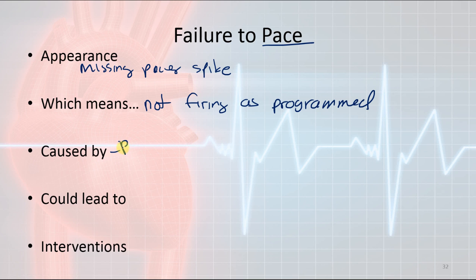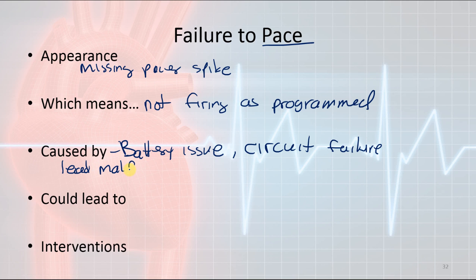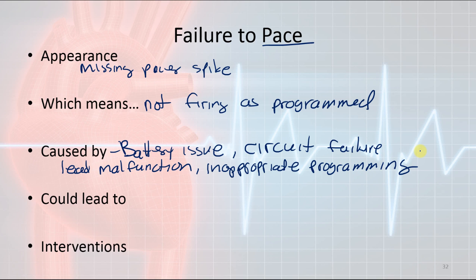This can be caused by battery issues. There could be a circuit failure within the pacemaker itself. It could be a lead malfunction. It could also be inappropriately programmed. There could also be, and this isn't much of a problem anymore, some kind of electromagnetic interference. Electromagnetic interference used to be a huge issue, and sometimes that's why when you walk into certain areas of buildings, it'll say something like microwave in use, because that would interfere with a pacemaker. Nowadays, there's much better electronic shielding, so it's not as much of an issue, but it still could be an issue.